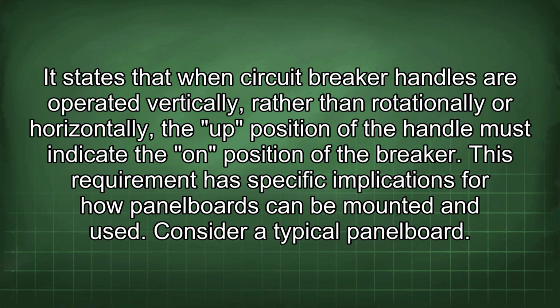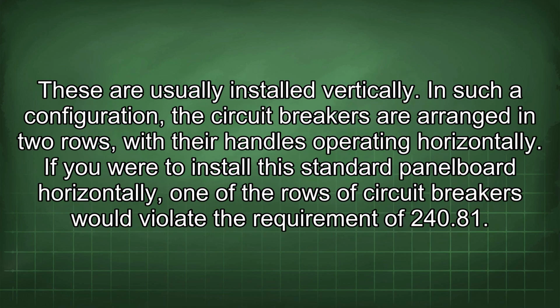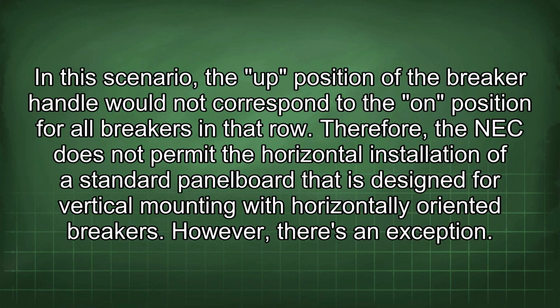Consider a typical panel board. These are usually installed vertically. In such a configuration, the circuit breakers are arranged in two rows, with their handles operating horizontally. If you were to install this standard panel board horizontally, one of the rows of circuit breakers would violate the requirement of 240.81. In this scenario, the up position of the breaker handle would not correspond to the on position for all breakers in that row.